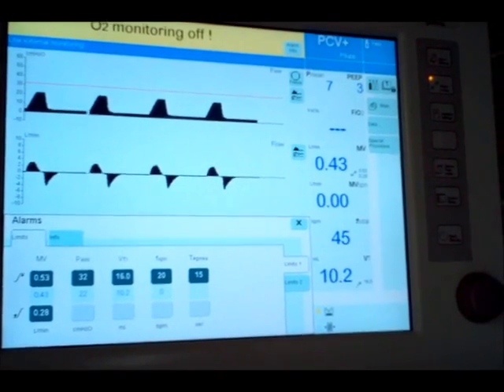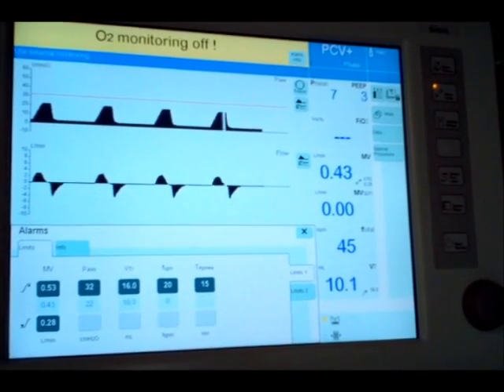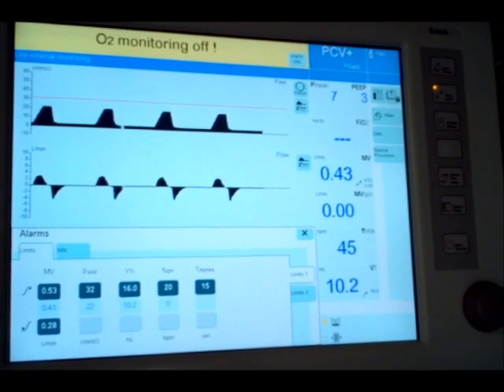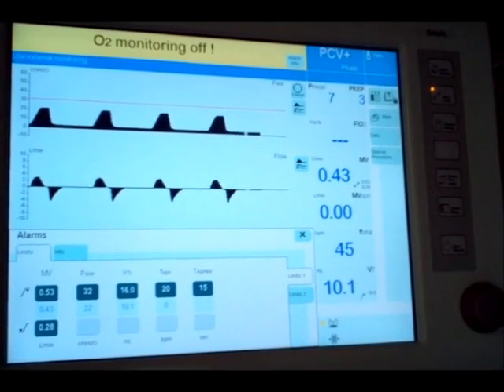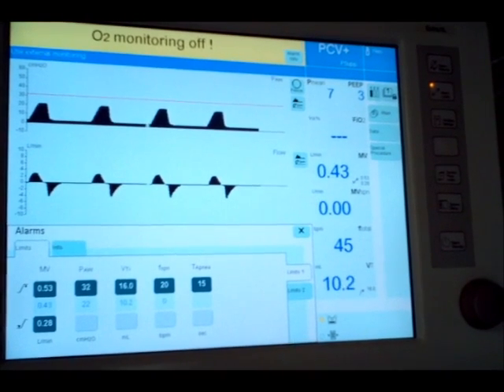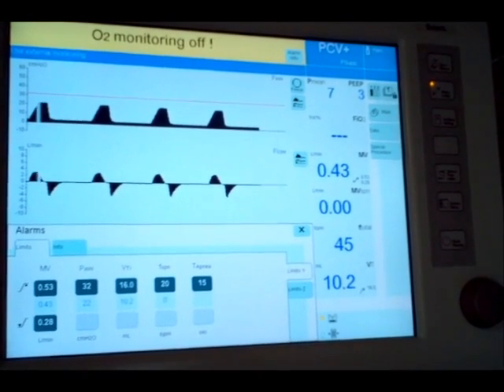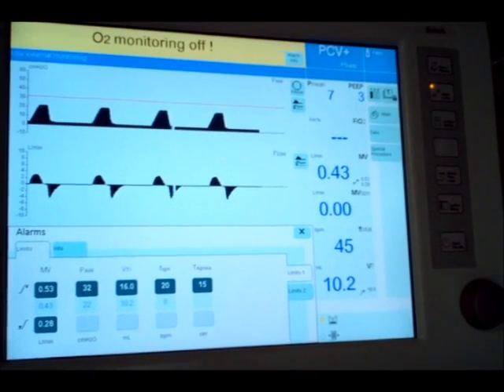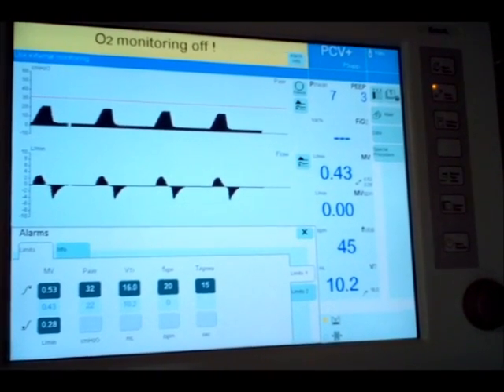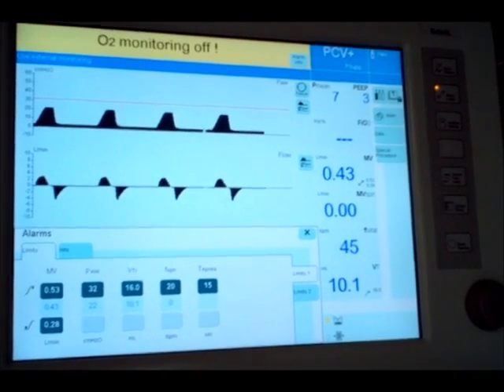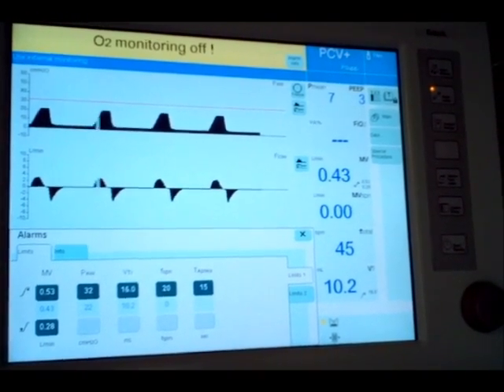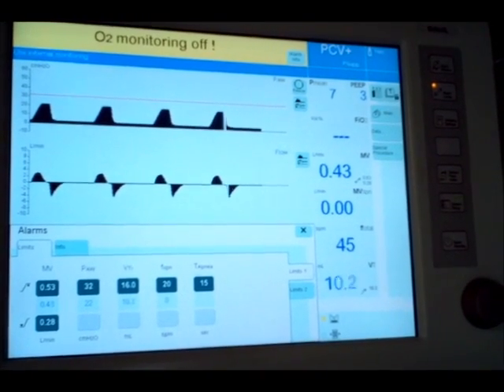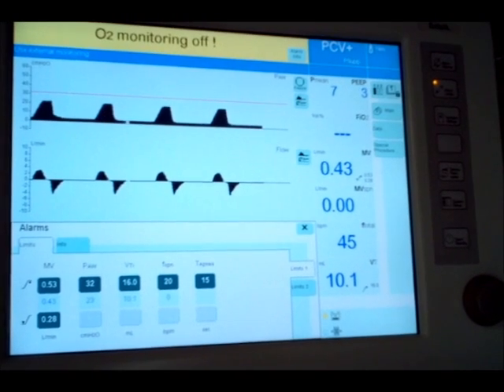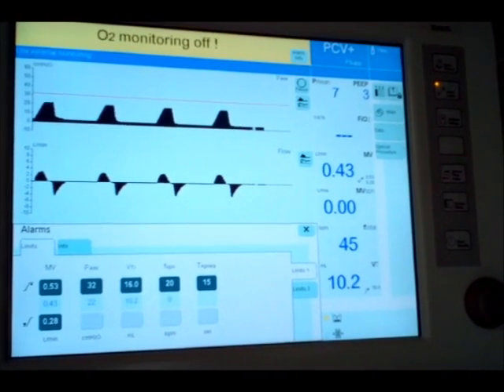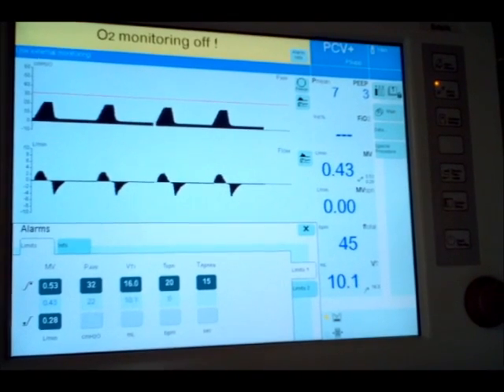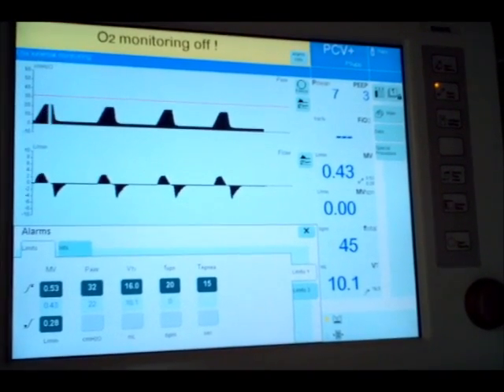Okay, when do I want to know about something? When do I want the ventilator to tell me about something? It's pretty stupid. It's only going to alarm when I tell it to, or when I set the parameters. So you can't read my mind at all. So it's up to you to set them, and you're not going to get orders on where to set the alarms. It's going to be entirely up to you. This will probably happen to you: you'll set them where you want them for your shift, you'll come back tomorrow, and somebody's changed them, which is their prerogative, okay? So you might want to change them back to where you like them. It's your responsibility to take care of that patient for the next 8 or 12 hours. Take care of them the best way you can.